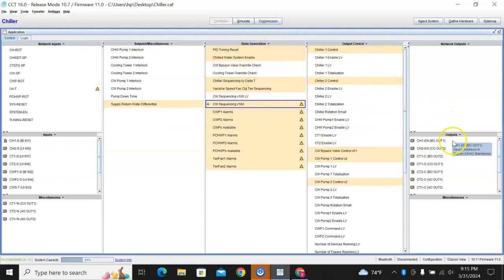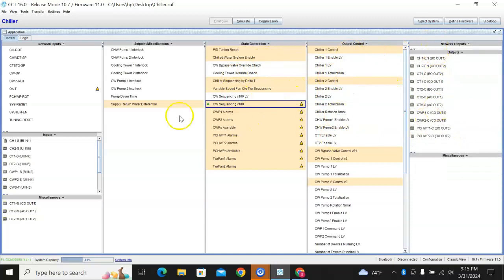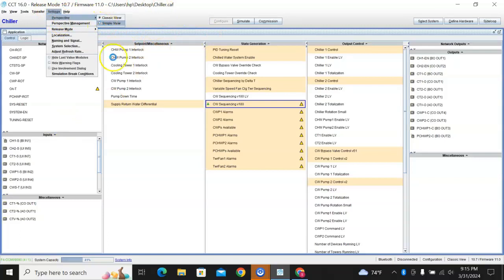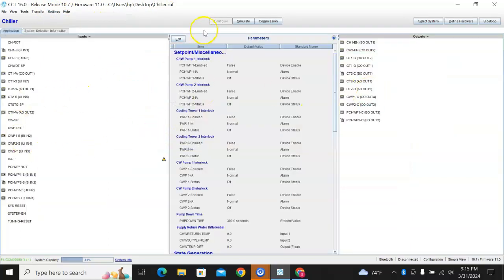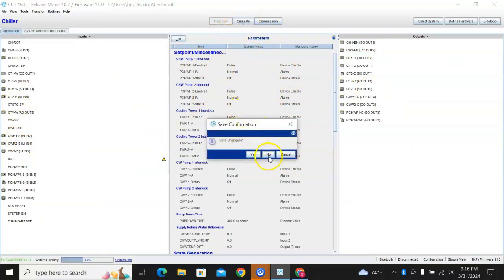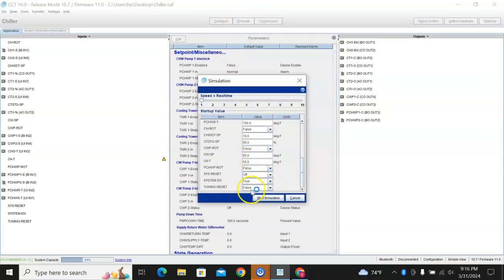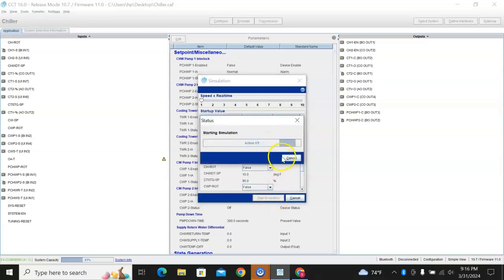So with just those changes there, I'm going to simulate this. I'm going to put it back in the other mode. That way I can hit the everything on. I'm going to go ahead and hit simulate, save changes. No. I want the system enabled. Yes. I want to start with my cooling tower set point at 85. Yes. I want my cooling tower temperature to be 85, and that's all I care about. So start simulation. I'm going to wait for pumps to turn on.